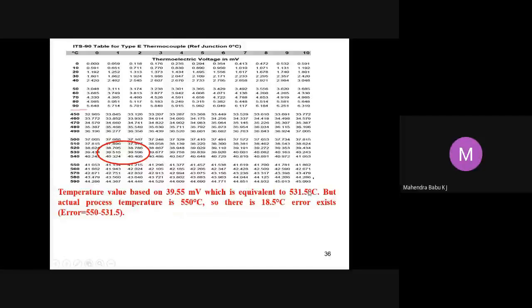But the actual process temperature is 550 degrees Celsius. Therefore, the error is 550 minus 531.5, which comes to around 18.5 degrees Celsius if you use this method. So we need to compensate for this. The temperature error will be compensated using cold junction compensation.